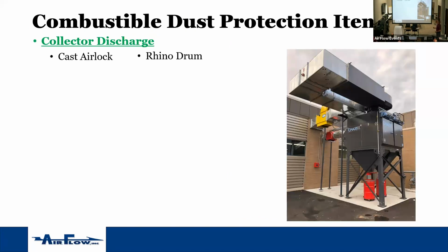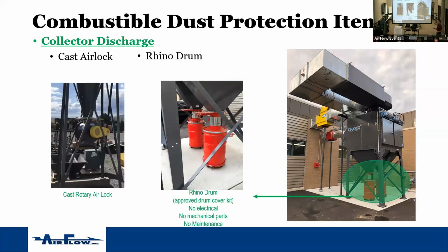On the discharge, we're going to talk about the discharge coming off the bottom right here. So that has to be protected. And there's two more common ways of doing it. One would be using a cast rotary airlock, an NFPA approved cast rotary airlock, or a Rhino Drum. The cast rotary airlock on the inside of it has no direct line of sight from the discharge hopper into the drum itself. So that will stop any explosion coming through. And if you haven't seen the inside of a rotary airlock, it's just a series of baffles and a star, and they just rotate. Picks the dust up at the top, rotates through, and dumps the dust out on the bottom side. But it's always sealed from the hopper to the drum.